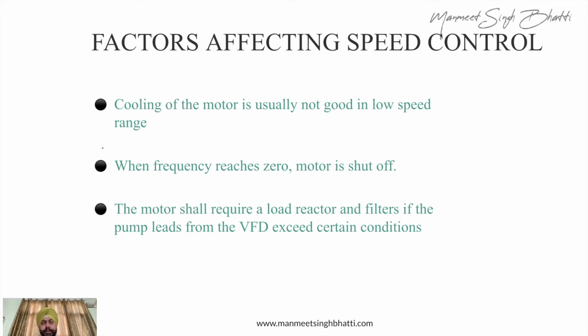So it's always recommended, whenever you are putting VFDs in an application where safety is very important for the machinery, that you lock the VFD for a minimum RPM. The RPM should not drop below that irrespective of any conditions. Otherwise, if the RPM goes below that, the motor will switch off, your load will be off, and there could be some kind of a problem in the system. Then the motor may also need load reactor and filters sometimes.